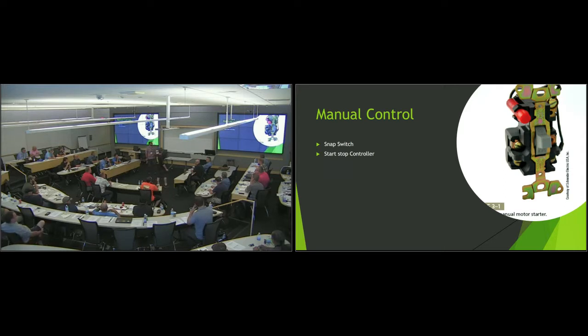Start-stop controller—this is what we refer to as three-wire control, meaning you'll physically need three wires in that pipe to operate it from a remote station. Start-stop is simple: two push buttons, one labeled stop, one labeled start.